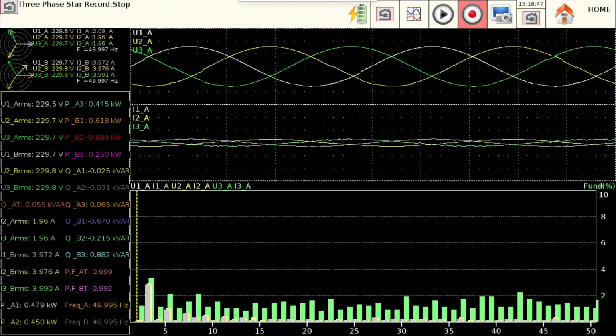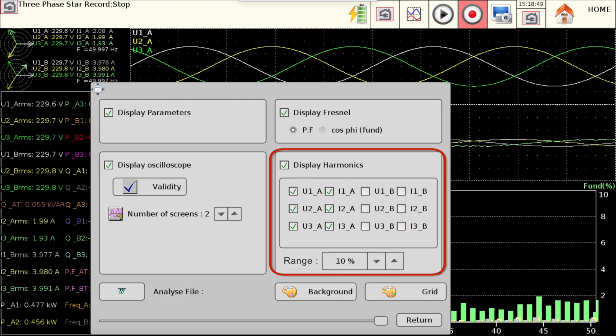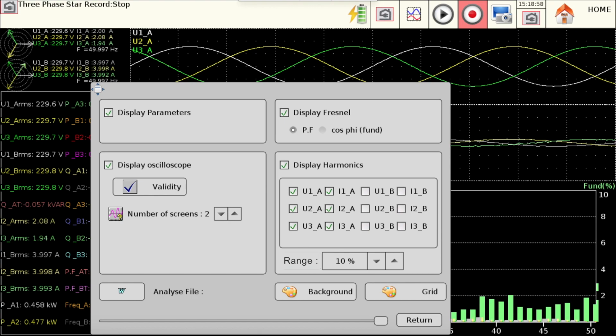Let's move on to the display harmonics. We can choose to display the voltage harmonics of circuit A, the current harmonics of circuit A, both of them, or even all the harmonics of the two networks. Range allows to define the display range in percentage of the harmonics diagram.